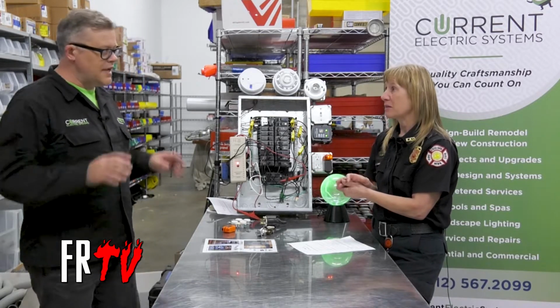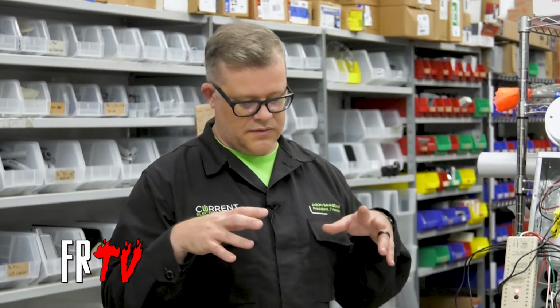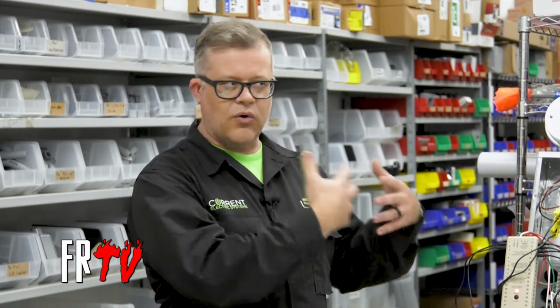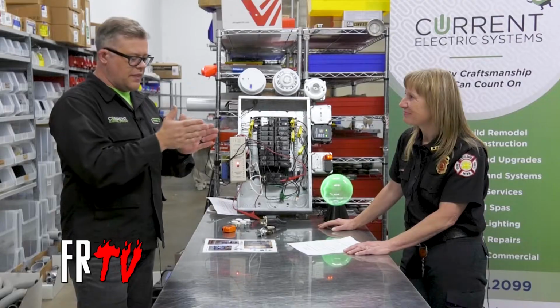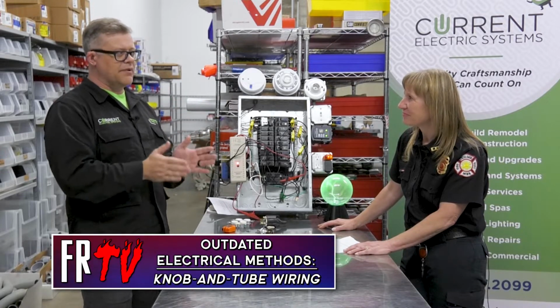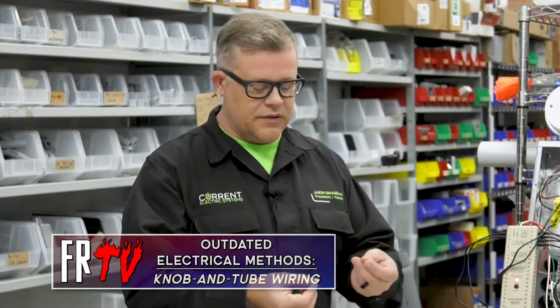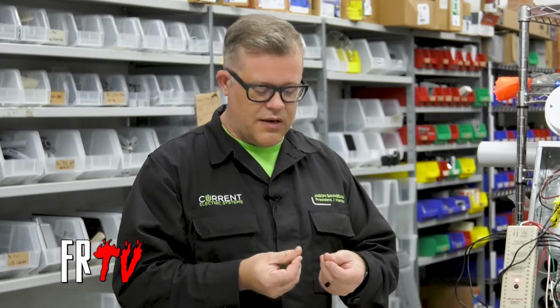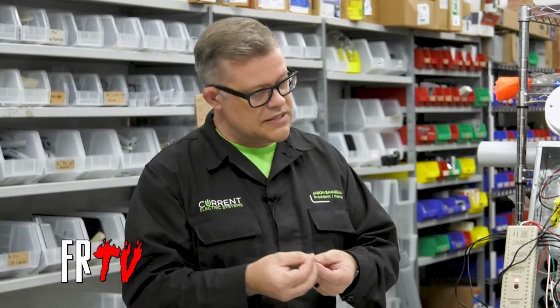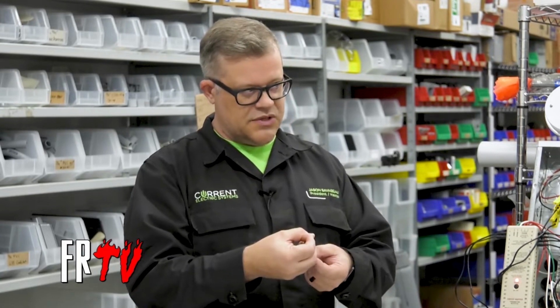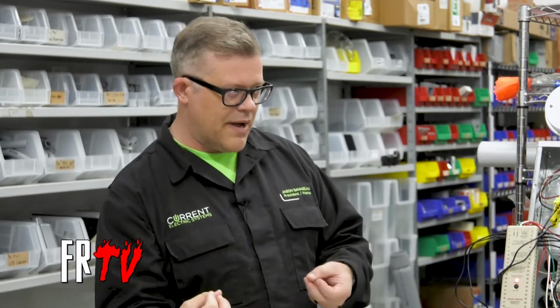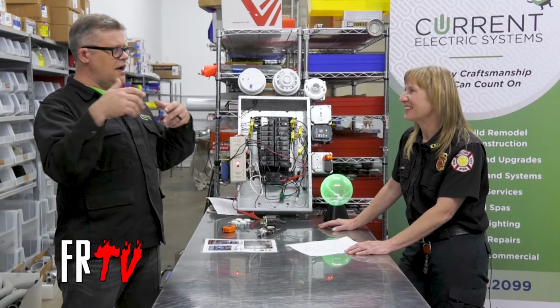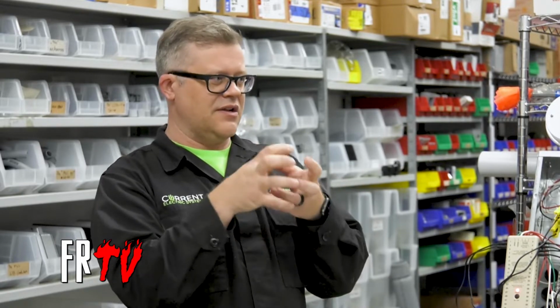Actually, Underwriters Laboratories did a study on this recently, collecting data on homes being demolished and the various older types of wiring methods used. The first iteration is called knob and tube, which you may have heard of. It's a cloth and rubber compound used to insulate the wire, and because rubber was used, they had to coat the wire in a zinc compound to keep it from corroding. When they were installed, they were done well, but now we have splices that are not in enclosures.